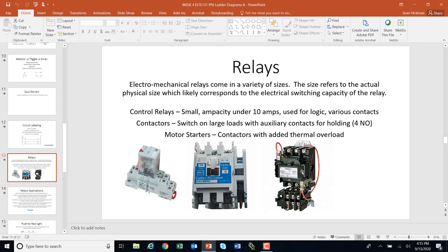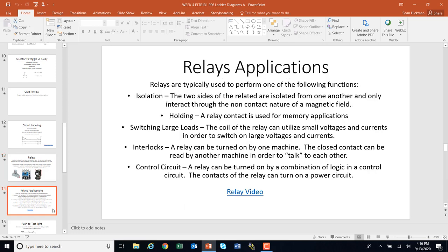Motor starters are like the Cadillac — shown here in IEC versus NEMA variations. A motor starter is a contactor with thermal protection added on, so it has an overload. It's basically a big relay switching a motor with high ampacity and thermal protection built in. Relay applications include isolation, holding, and switching large loads — you can switch a very large load using a relay — as well as interlocks and control circuits. Go ahead and stop and watch this relay video about the operation of relays.